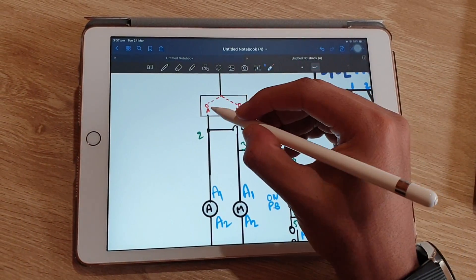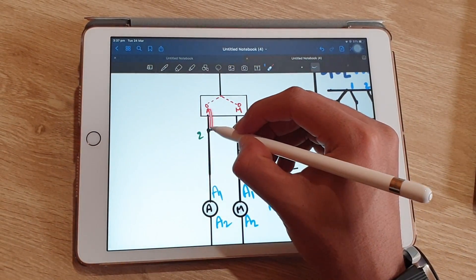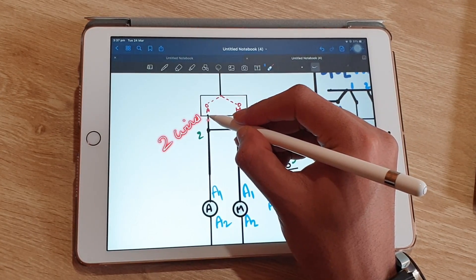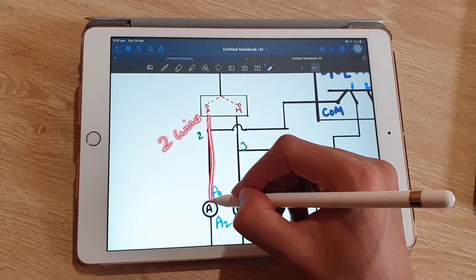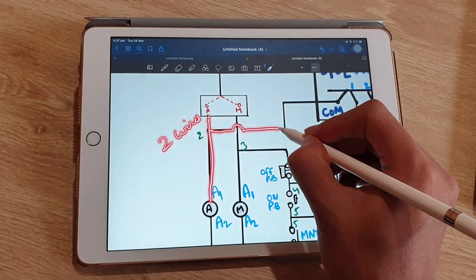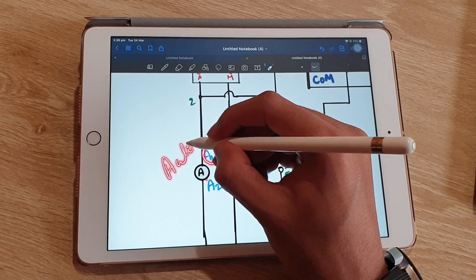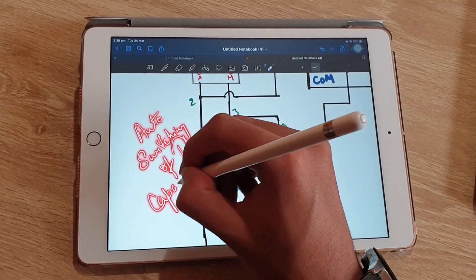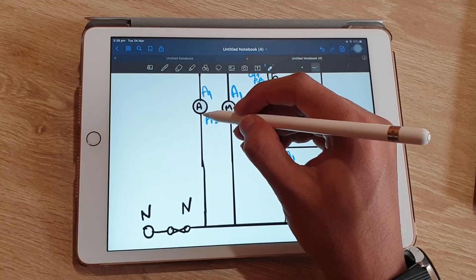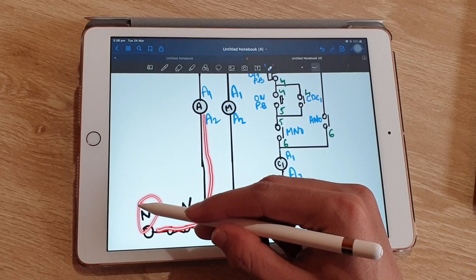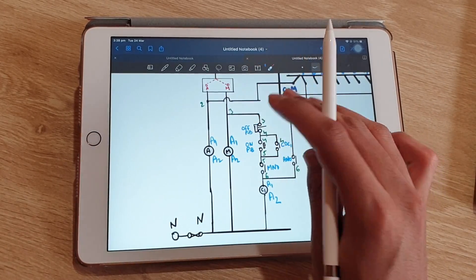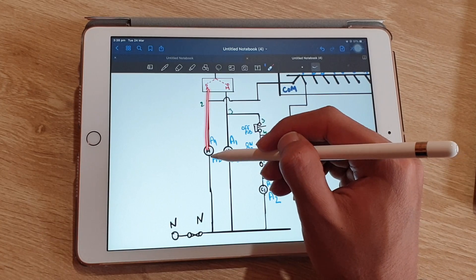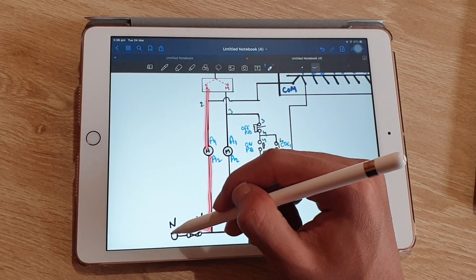From the auto terminal of the auto-manual selector switch, two wires are taken out: one wire is connected to the auto contactor, which is used for auto switching, and the other wire is connected to the common terminal of the APFC relay. The A2 terminal of this auto contactor is connected to neutral.